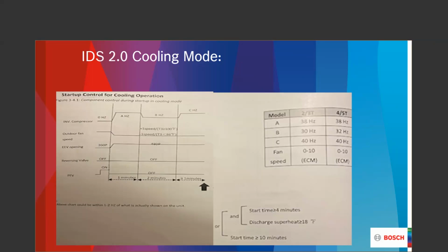So here we are, we've got the fan motor started. And what we're going to be looking at is an increase of fan speed based off of a liquid line temperature. And that liquid line temperature, and you'll see here in just a little bit, is literally based off of a pressure. We understand through Boyle's law that every time there is a pressure given, there's a temperature that's going to be related to that pressure.